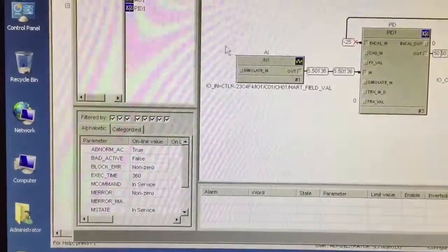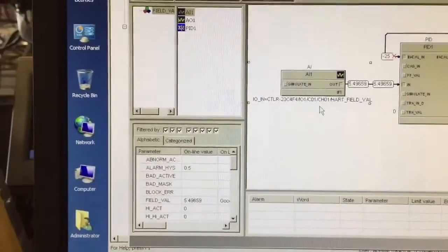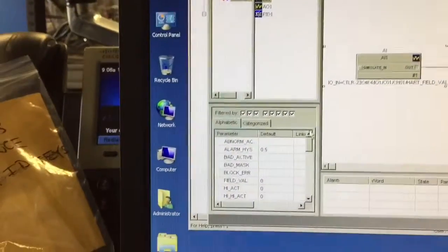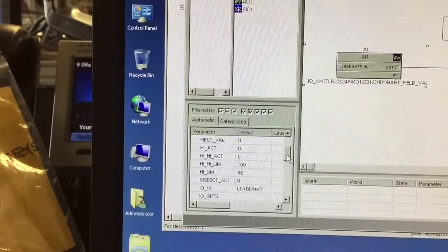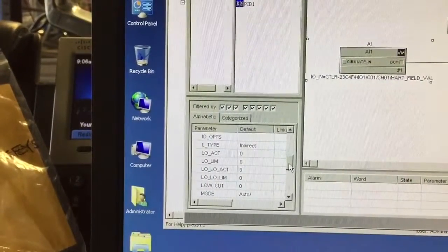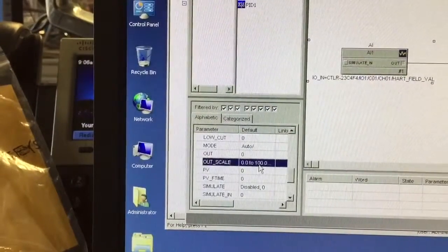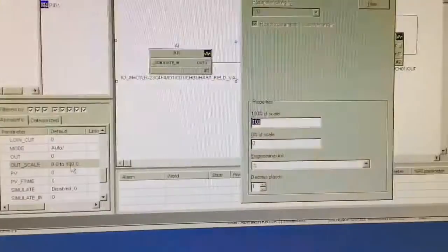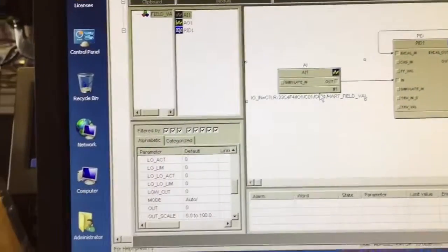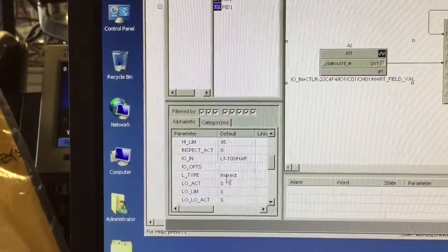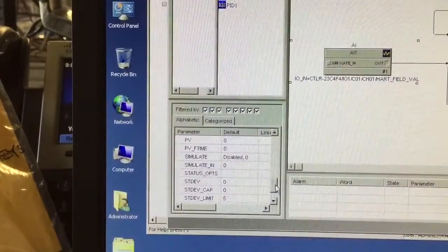So I'm going to take you over to the computer here. In DeltaV right now, this AI block right here is used for scaling. We're going to go offline, click on the AI block. I've selected it and I've got all these check boxes, all the filters checked on. If I scroll down to our outscale, right now our outscale is set up for zero to 100%. So the outscale of the AI block is set for zero to 100%. We are using an L type of indirect, so we're doing a range conversion in the block, scaling.